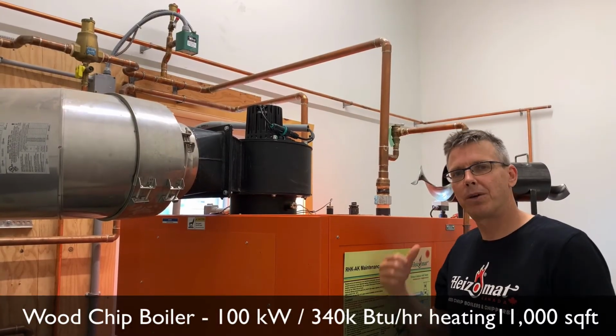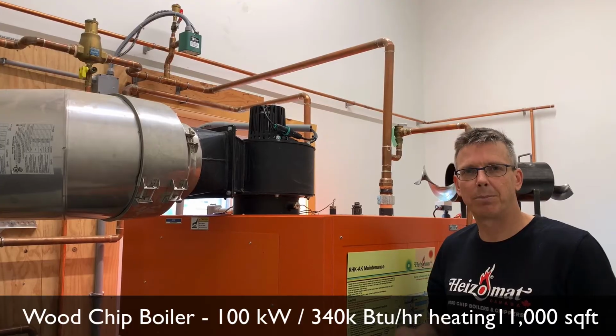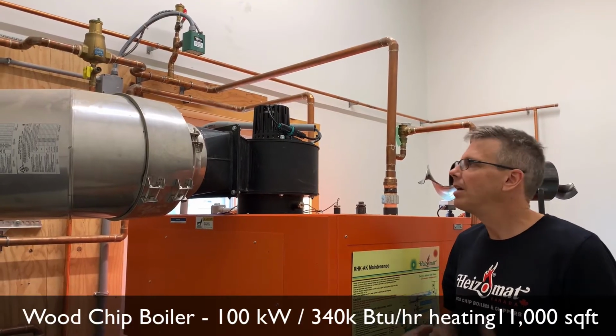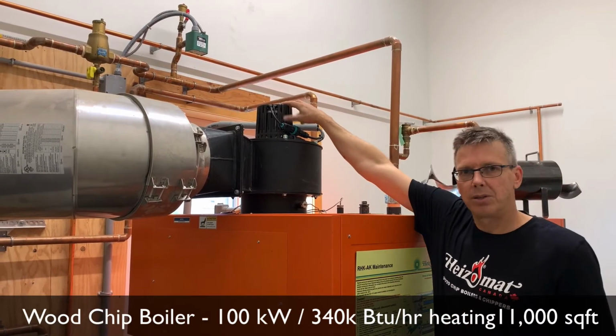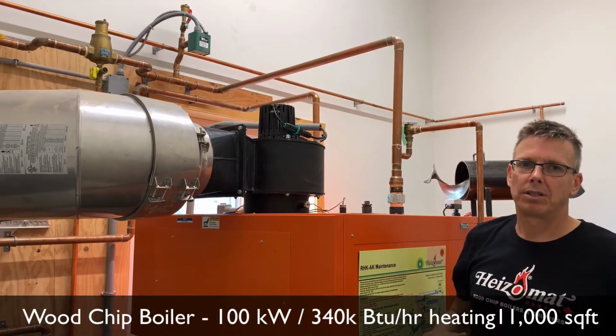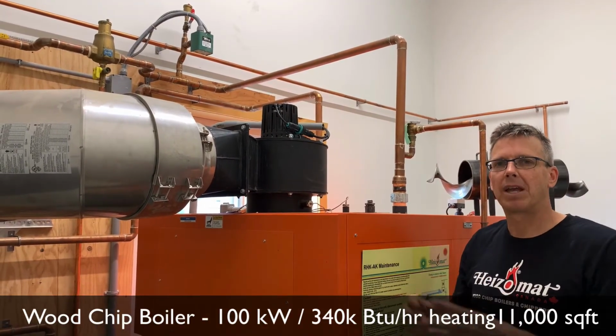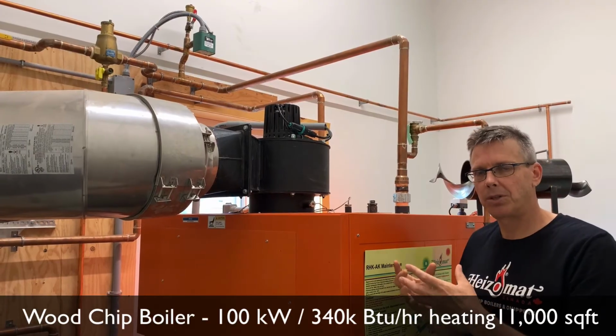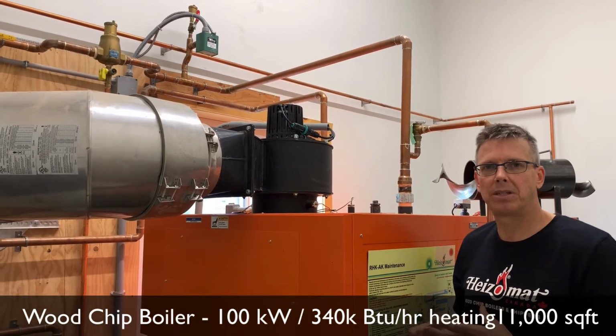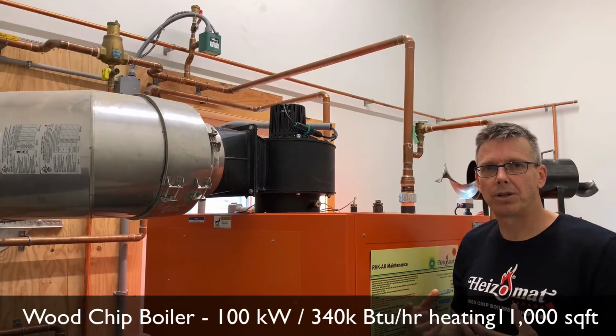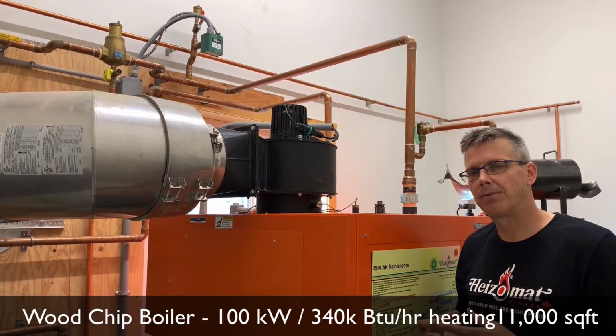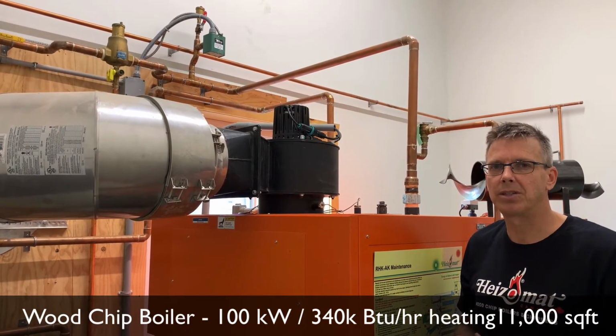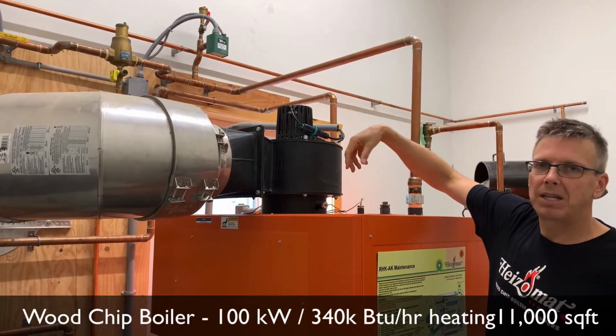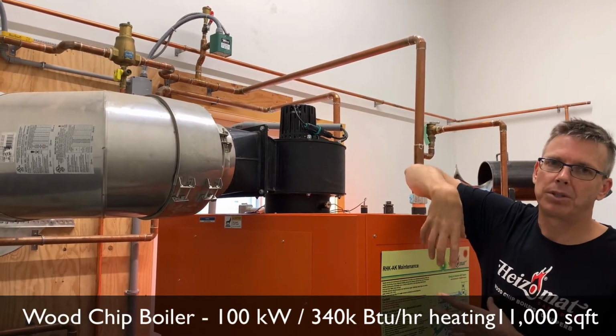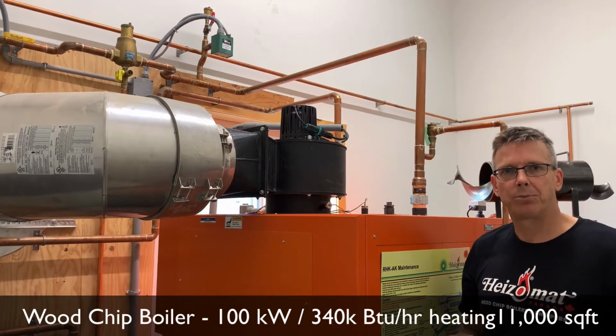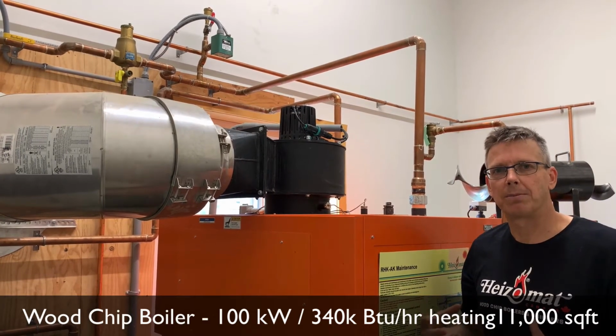In addition to the two blowers that we looked at at the front of the boiler that supply the air directly onto the fire bed, we have a flue gas blower which is on the exhaust. So what this is doing is it's assisting the draw of the boiler out the chimney. The temperatures going out the chimney are not particularly high compared to something like a wood stove. They typically are around the 140 to 160 degrees Celsius range. And what this does is it makes sure that we get enough negative pressure inside the boiler. As soon as we get positive pressure, that's when we can get smoke, that's when it becomes dangerous.